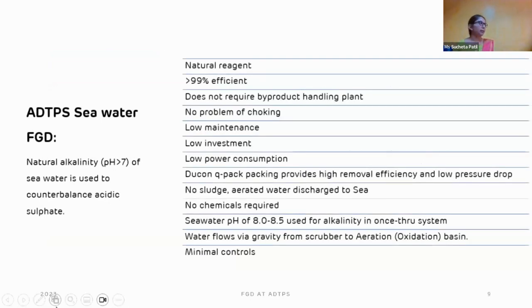As we discussed, the main important thing is the natural reagent and natural alkalinity of seawater, which is 99% efficient. It does not require any byproduct handling system, no problem of choking. Also, it is low maintenance, low investment, and low power consumption. The packing material provides high removal efficiency and low pressure drop. No sludge, aerated water discharged to sea, no chemicals required. Seawater pH being between 8 to 8.5, which is alkaline, is used for removal of SO2. Water flows via gravity from scrubber to aeration basin and minimal controls are required.